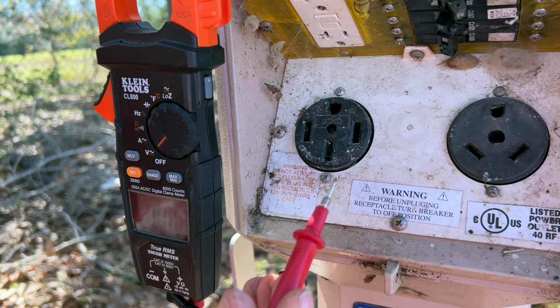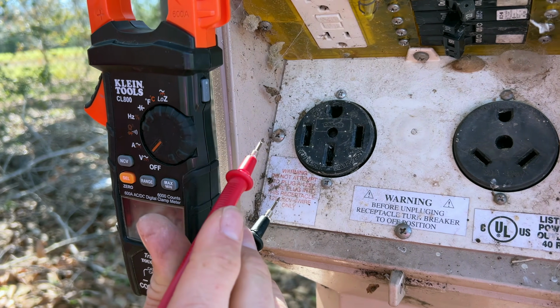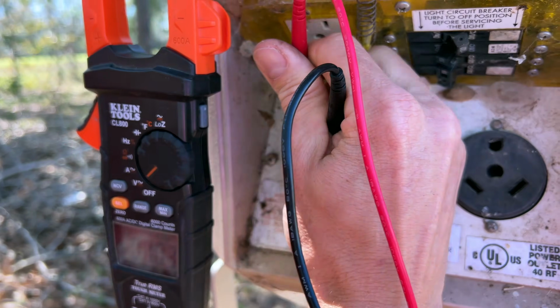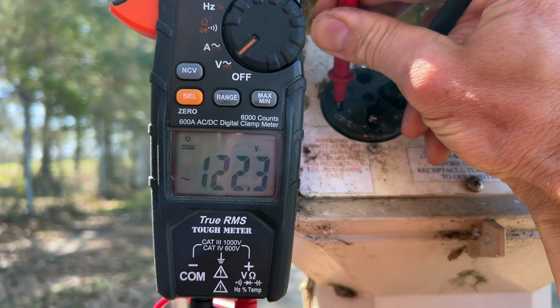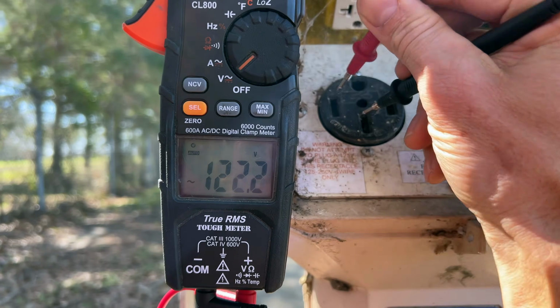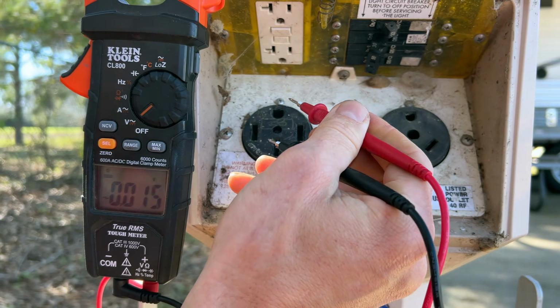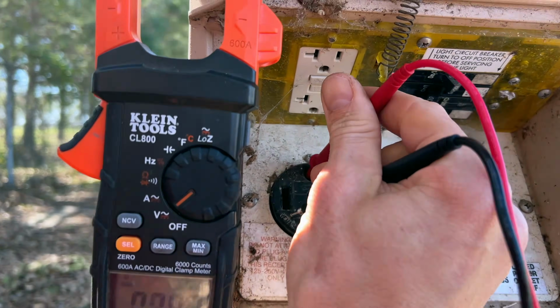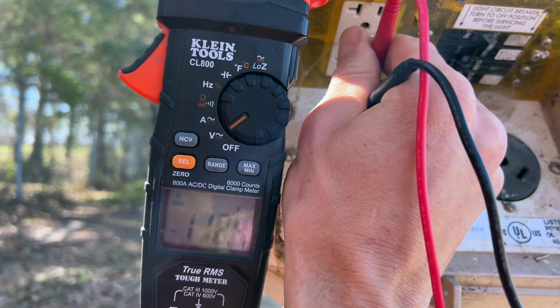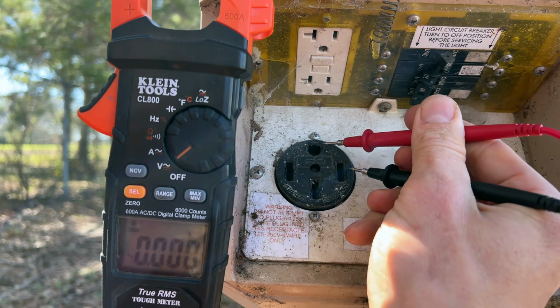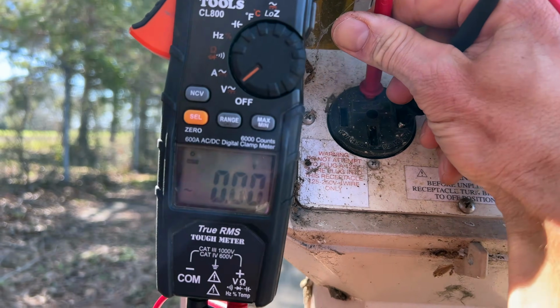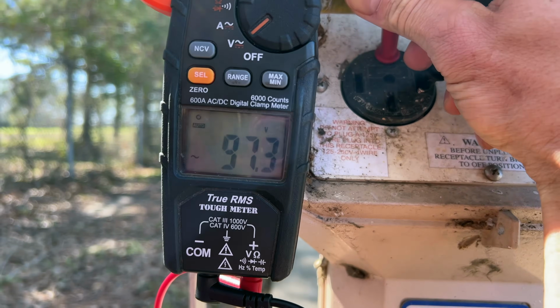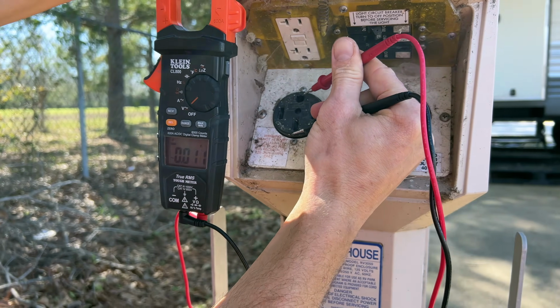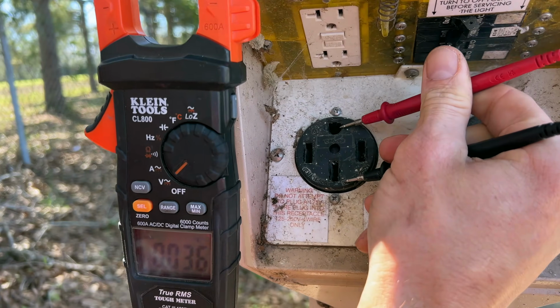So we're good there. Now we'll test our neutral to our left hot leg. So black again on the bottom to neutral, red into the left hot leg. We're at 120 volts. Now if we do the same thing to our ground, so ground on the top, hot leg on the left, we should read 120. And our hot leg on the right, to ground on the top, should again read 120. Now we're going to check between our ground at the top and our neutral. This should be 0 again.